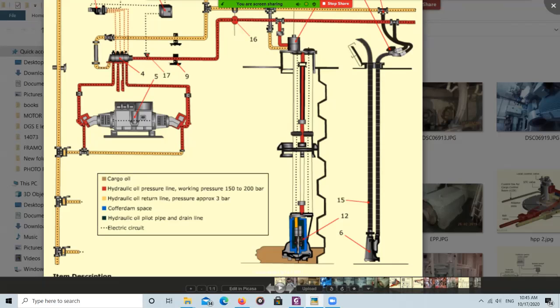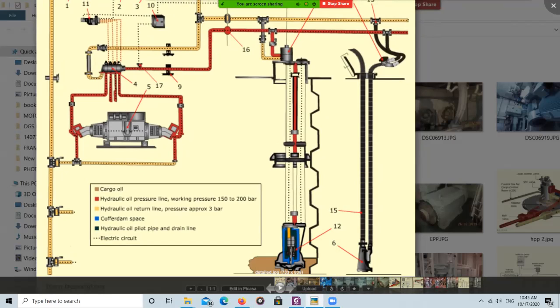This is the construction inside the tank: the cargo pump is at the bottom, and on top of it the hydraulic motor is located. This motor is also an axial piston type variable displacement motor. The portable Framo pump is used when the main pump is not working — it must be lowered into the tank for emergency cargo discharge. It connects to the main line using snap couplings, and there will be designated ports on the walls to attach these snap couplings.